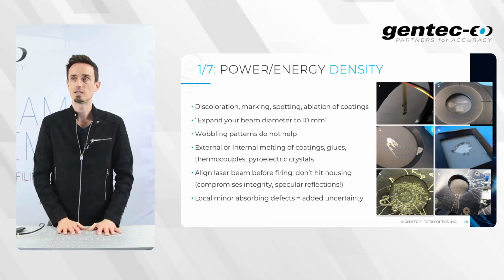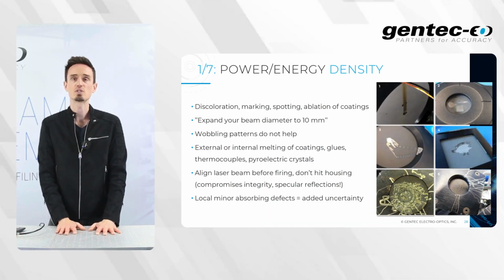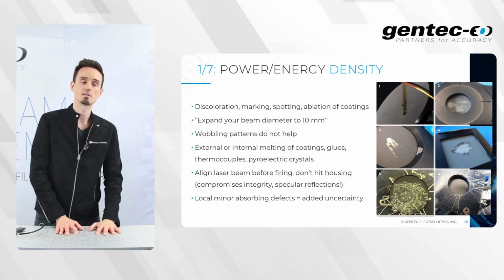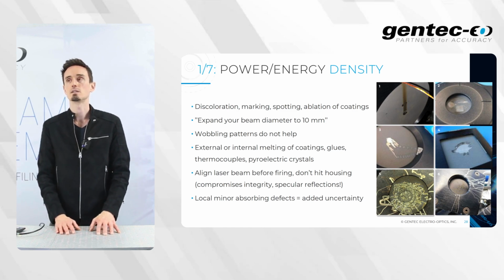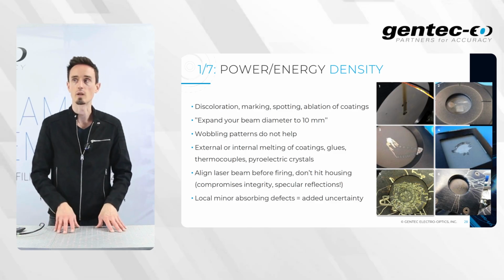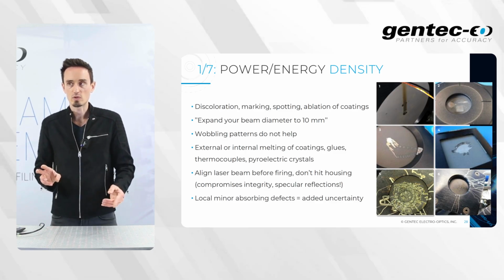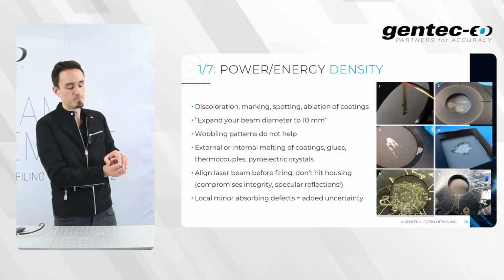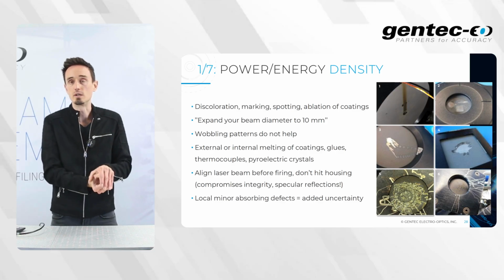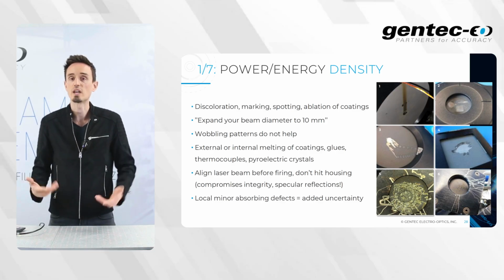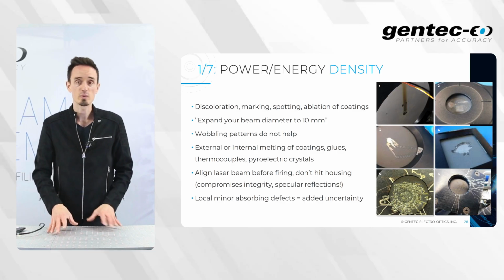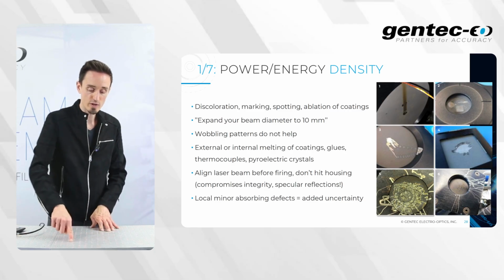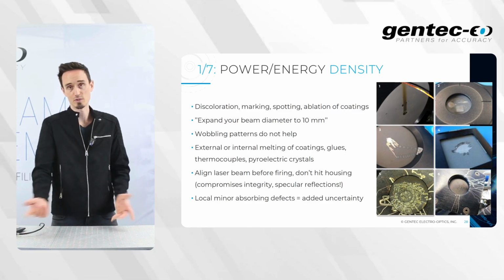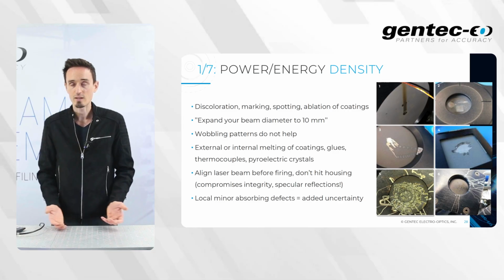First one, power and energy density. Please have a look at those pictures here. This is typically when detectors' surfaces get discolored, marked, get some spotting, ablation of coatings, and so on. Typically when we use, let's say, a 19 millimeter power meter, and we say expand your beam diameter to 10 millimeter. If you're not so familiar with that, it is common to program your laser engraver to draw a circle of 10 millimeter diameter. And we see that pretty often.